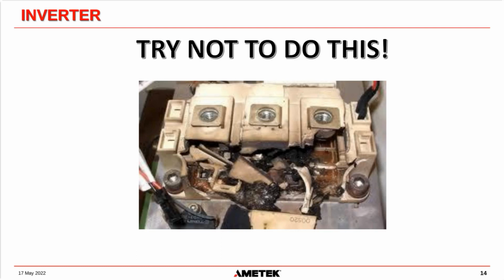Unfortunately, IGBTs are extremely sensitive devices to high current situations. There is no fuse that has been invented that is quick enough if, for some reason, you get a shoot through circumstance where both IGBTs in one leg are turned on at the same time. There is no fuse quick enough to prevent that high current from damaging the IGBT, and this is what happens. Obviously, this is an excessive detonation of an IGBT. In some circumstances, you won't even see the physical damage in an IGBT that has failed. But in most cases, you will see some cracks in the external cases. Okay.